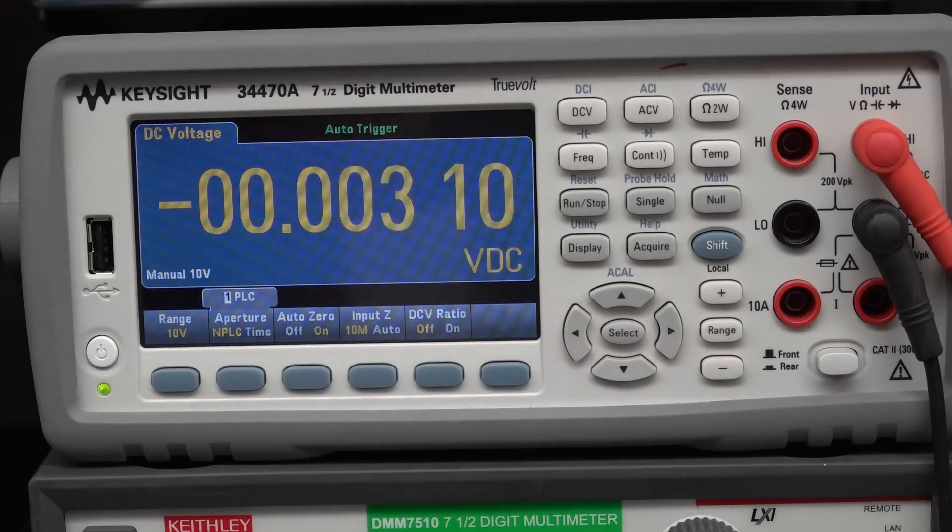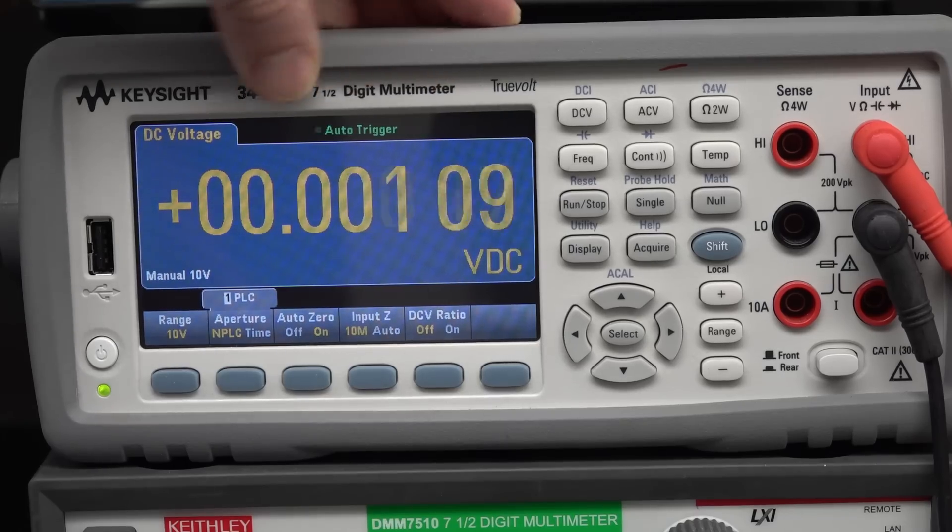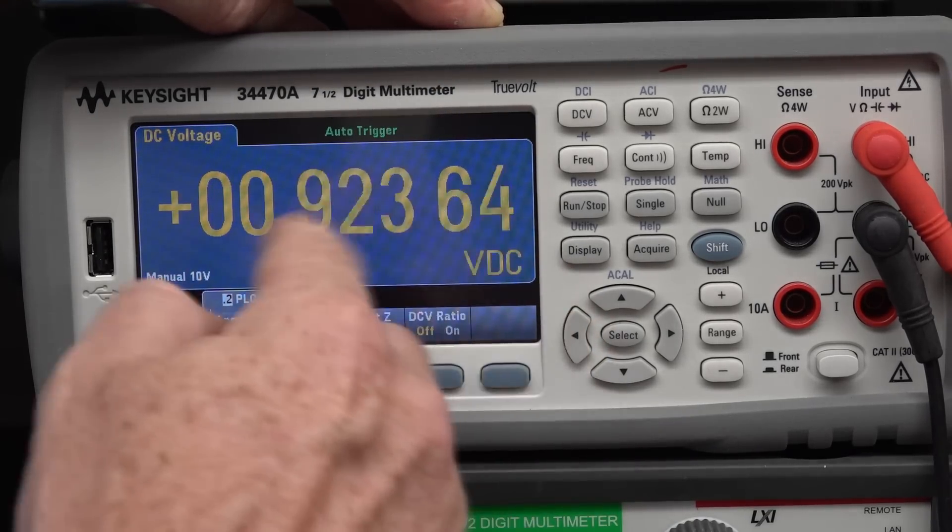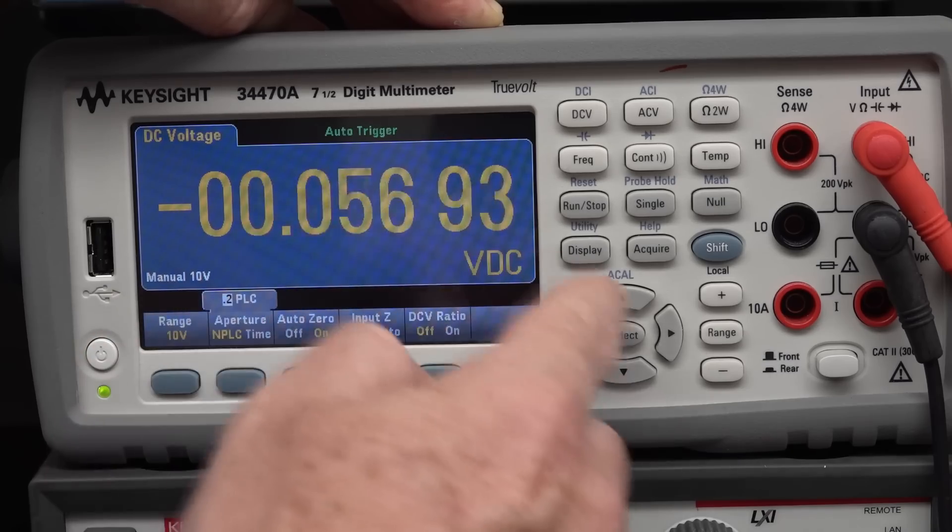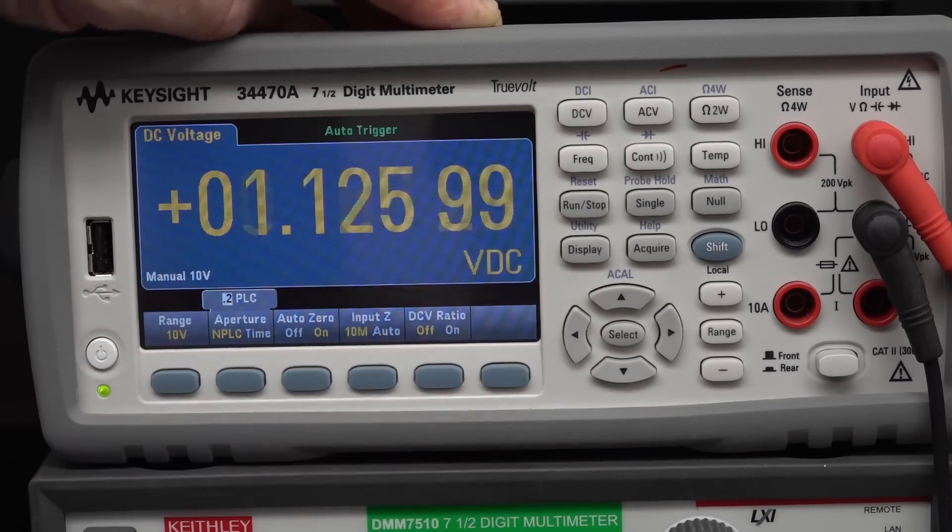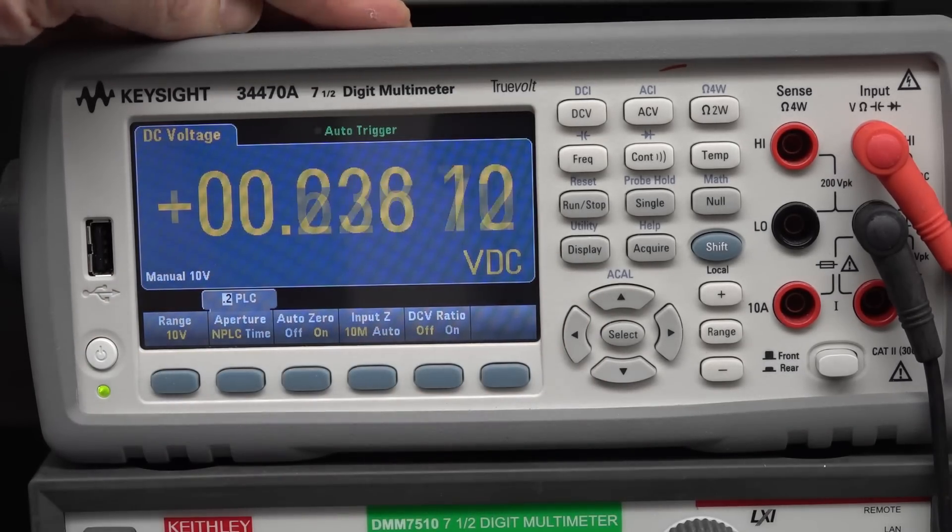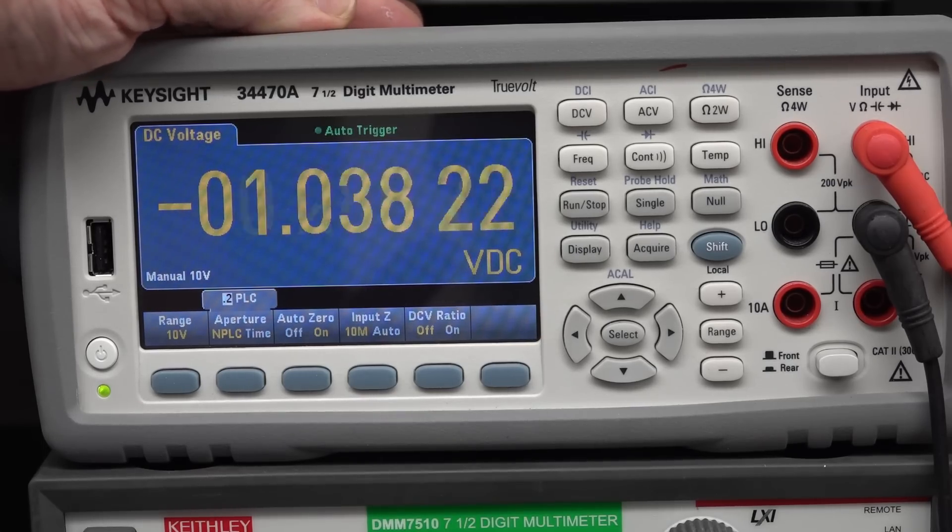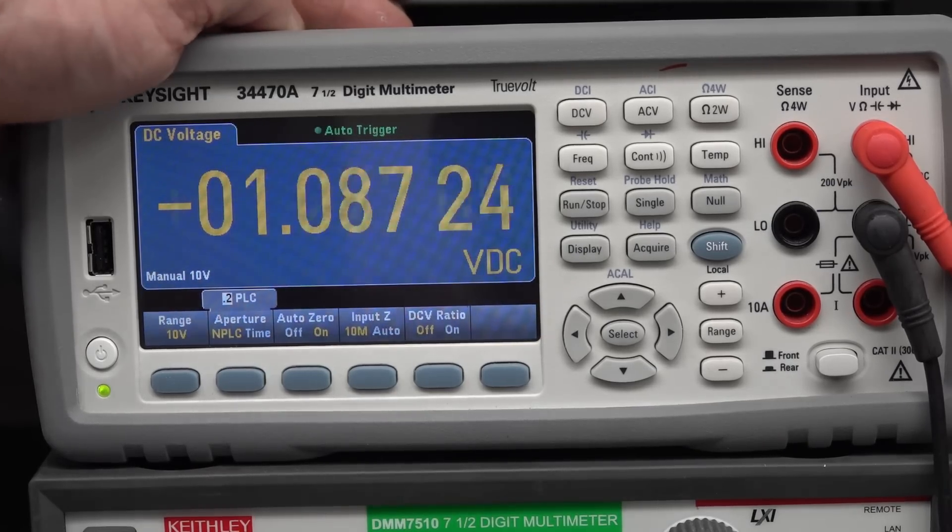And if I go into 0.02 power line cycles, 0.06, we're still getting volts of noise, right? And 0.2, we're still getting quite a lot of noise. But watch what happens when I go to one power line cycle. Ta-da! It's magically vanished. Because it's doing at least one full integration of the 50 or 60 hertz power line cycle. So, you're reducing the noise. And you can see, of course, that we've got more significant digits now.